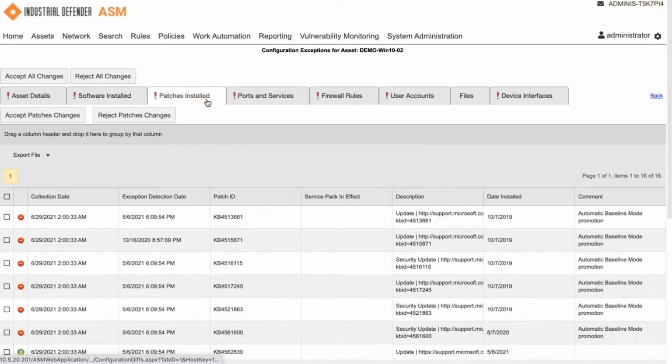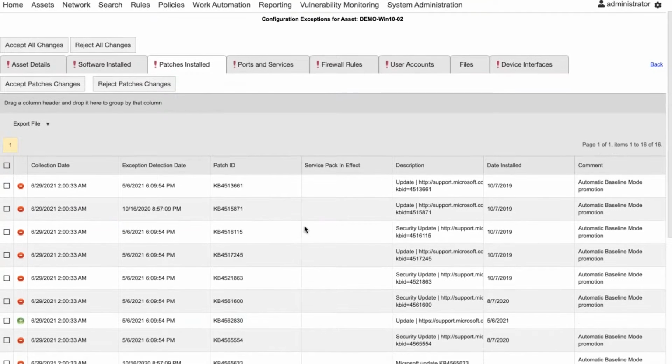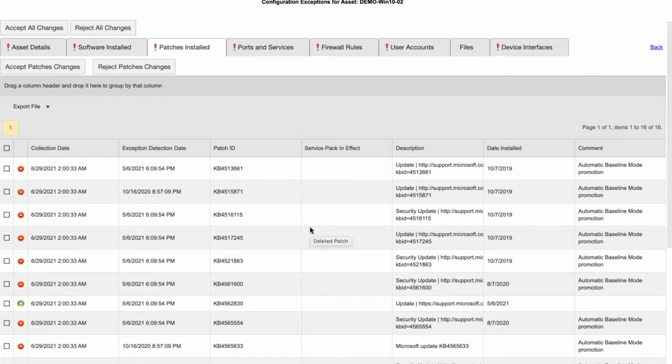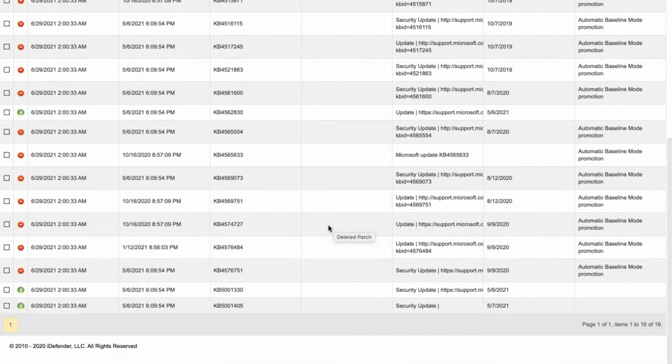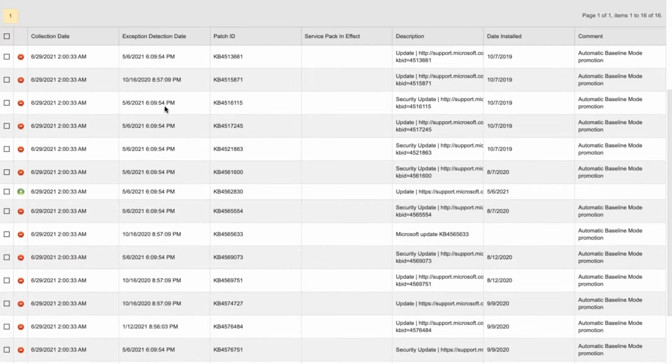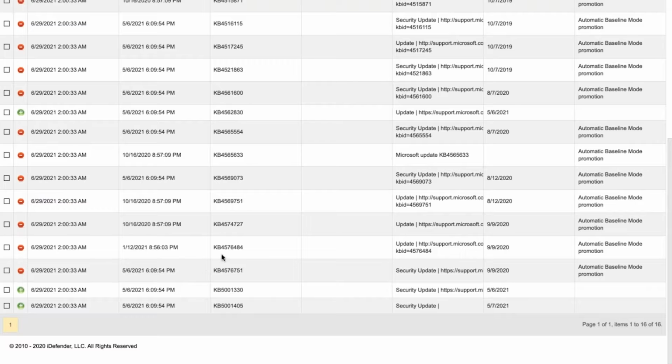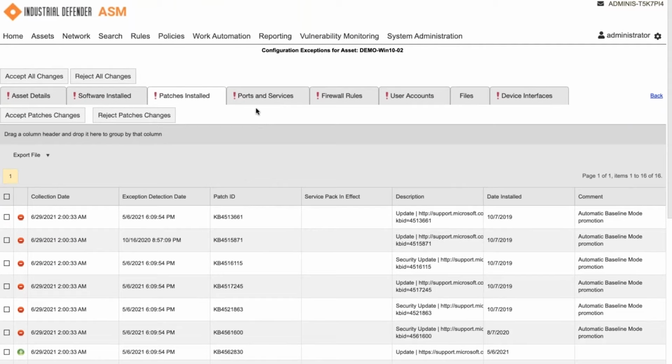And then if I come here, what I'm starting to suspect is this asset got patches, right? It got a set of unapproved patches that broke the HMI, which is very, very common. That's why you have to really test patches and really understand what's going on with your patching scheme. And so here we can see that, in fact, yes, several were replaced with what we call superseded. So another patch came along and replaced it, and these newer patches are here. Generally that's where I would then turn my focus and try to understand that, especially since the other HMIs in its group didn't have that notification. They're still working. I'd be able to quickly tell all of that information.